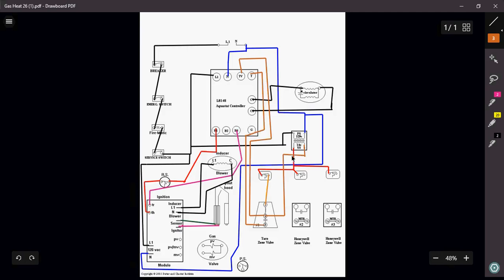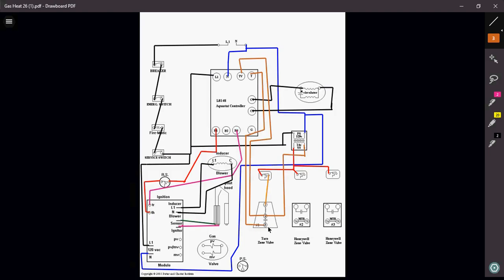So as this thermostat calls for heat, I am now going to power up my terminal one, which now is going to energize my motor. That motor is now going to start to heat up and melt that wax that is in there. And as that wax melts, my end switch will now close. So now between terminals two and three, I have now made a circuit, which will now tell my Aquastat that I have a call for heat. The Aquastat will send that signal down to the ignition module to send the call to my burners so that I can start delivering heat. But before we get to that part, let's take a look at the next two.